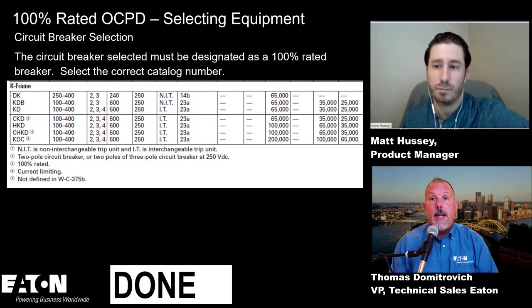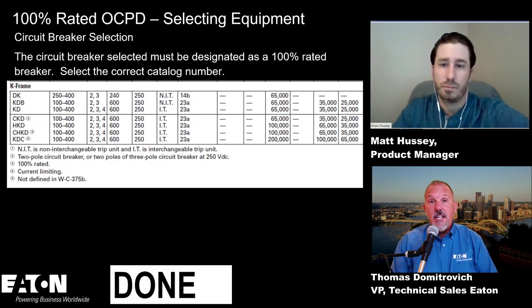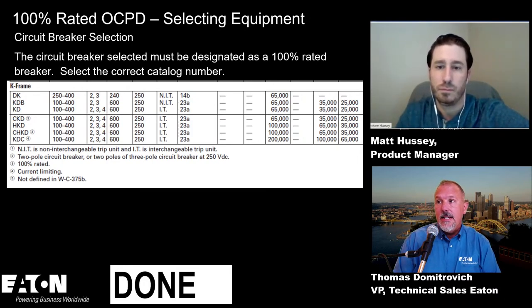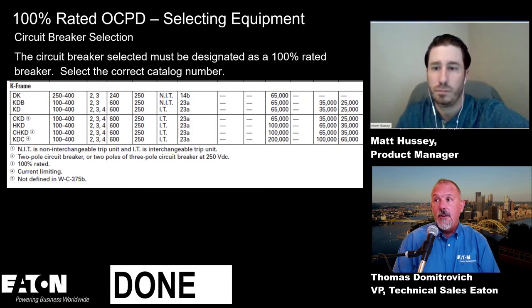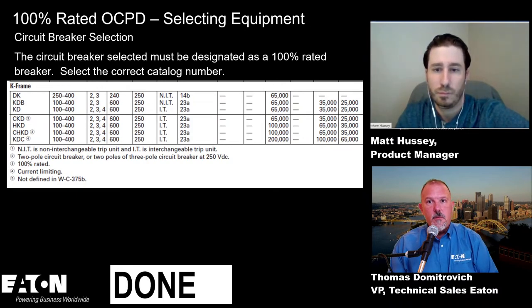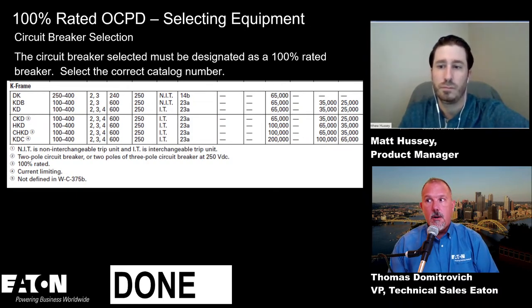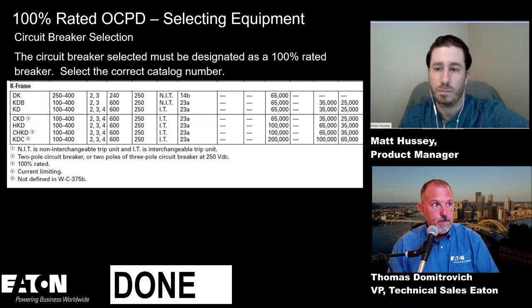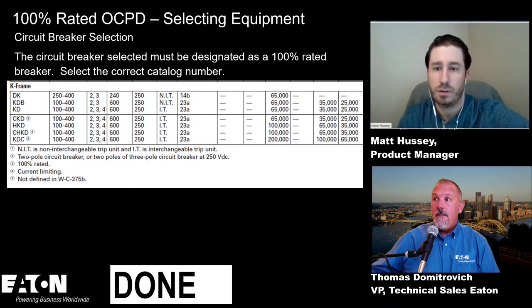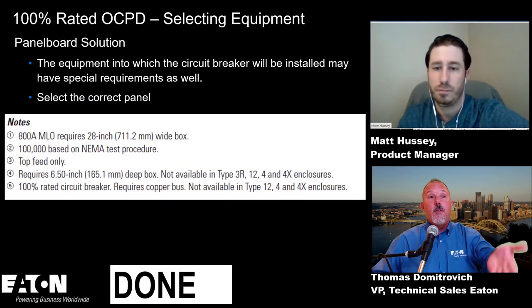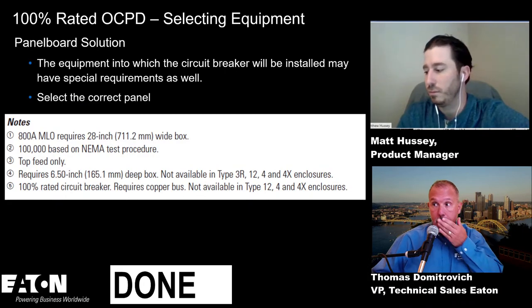That means you could buy that in 100% rating. The HKD is not. The CHKD is. The KDC is not. That is its current limiting. So not all circuit breakers are rated for 100%. So I may not be able to get a specific frame or a specific type of breaker if that's what it's called out for other reasons, right?